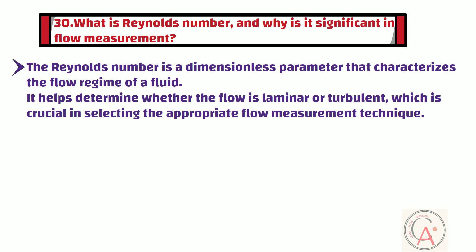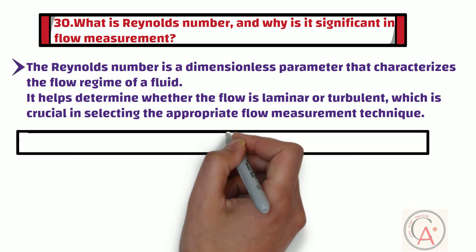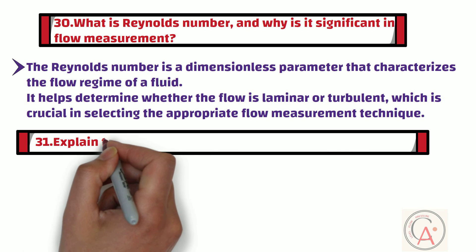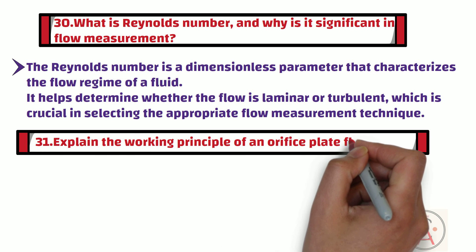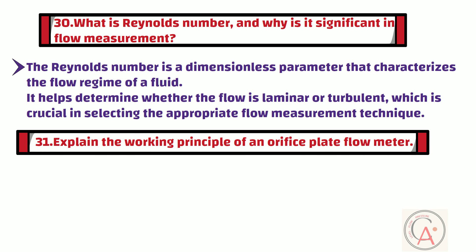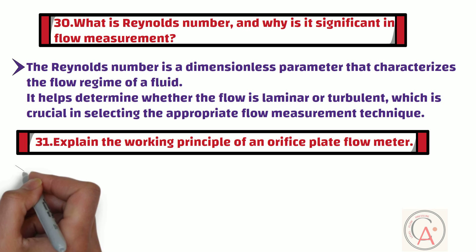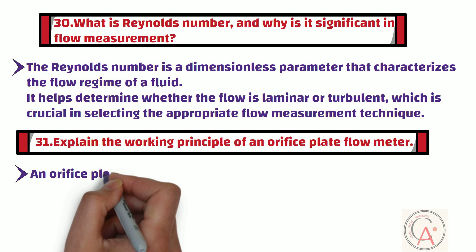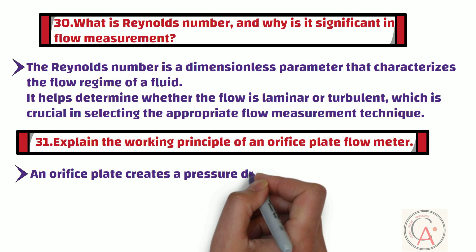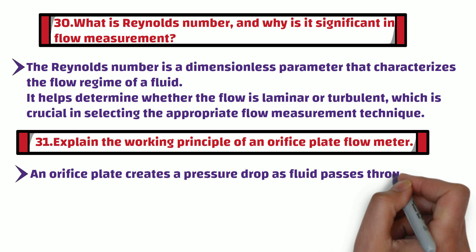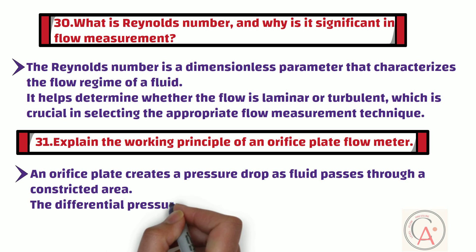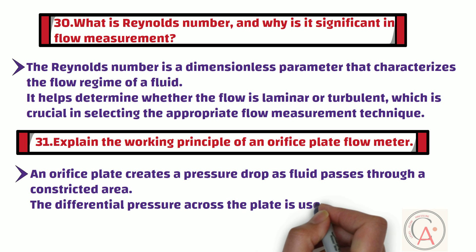The 31st question is: explain the working principle of an orifice plate flow meter. An orifice plate creates a pressure drop as the fluid passes through a constricted area. The differential pressure across the plate is used to calculate the flow rate using the Bernoulli equation.